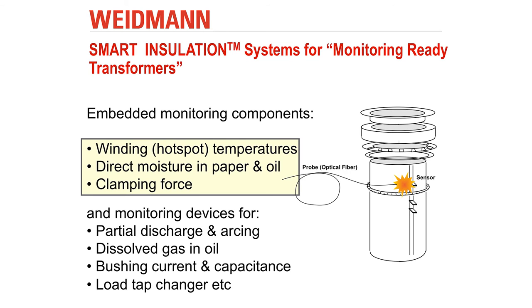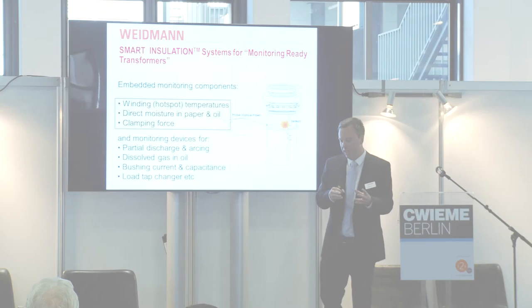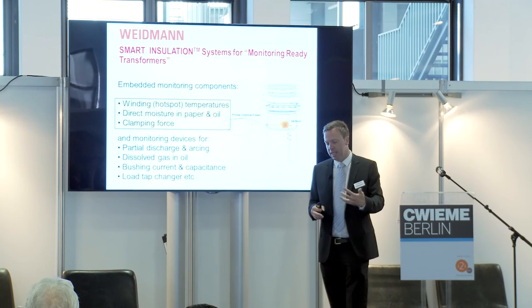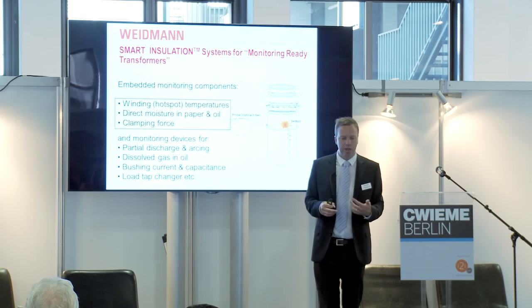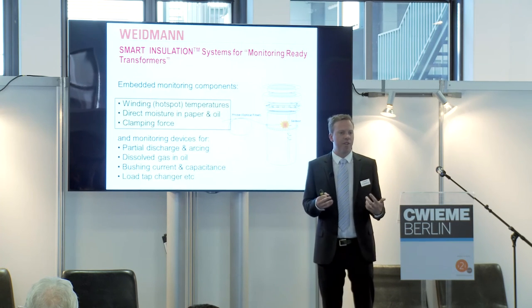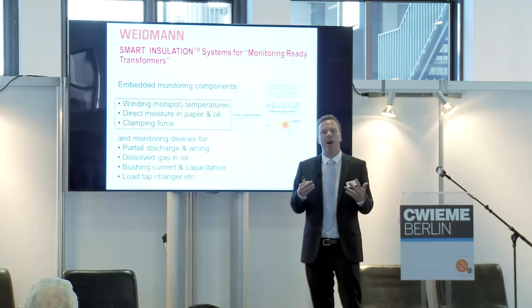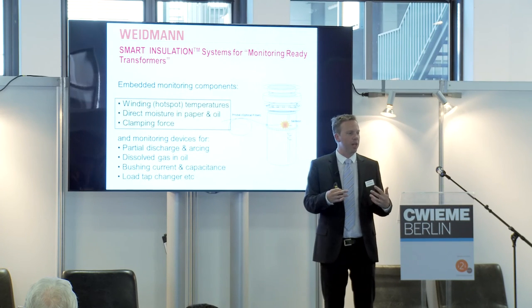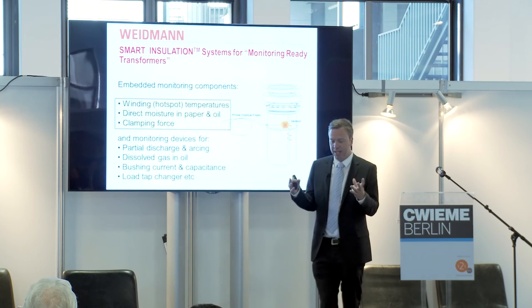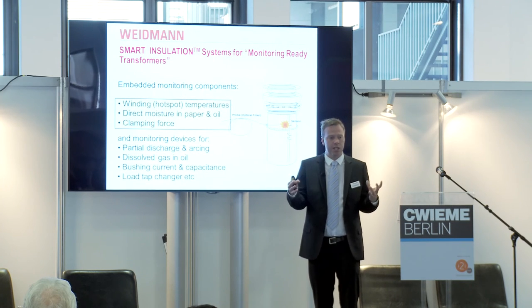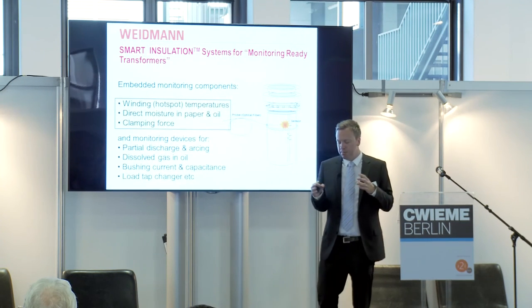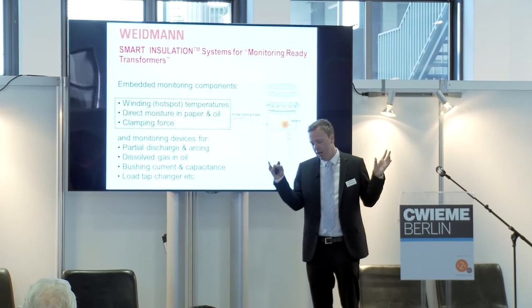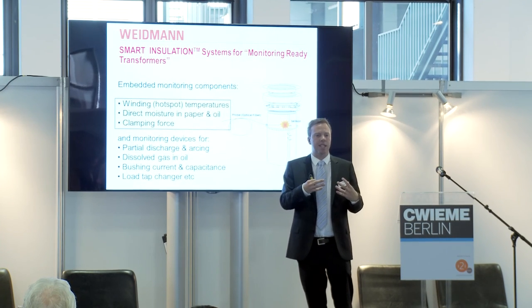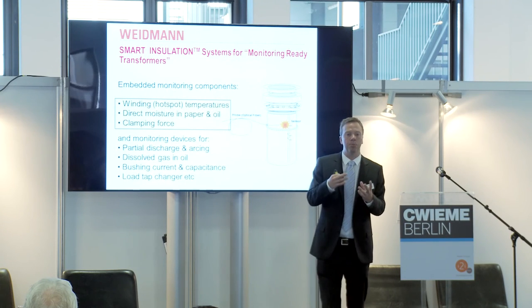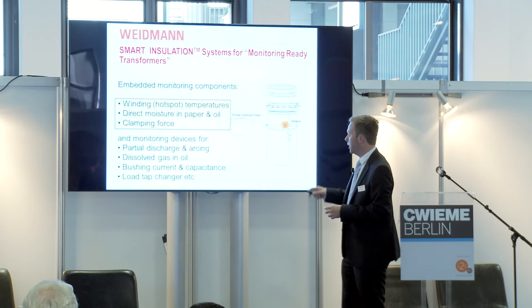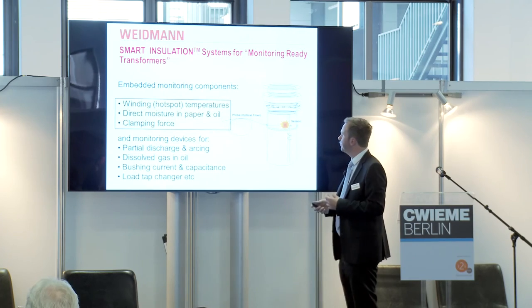We're not discounting other areas, of course. Things like dissolved gas in oil monitoring analysis online certainly has value and can provide further insight into what's going on in your transformer and what's creating problems that could cause it to fail in the future. Partial discharge, bushing monitoring, load tap changer and so on, all of these are key areas we fully accept can complement very much what we believe to be this embedded platform.